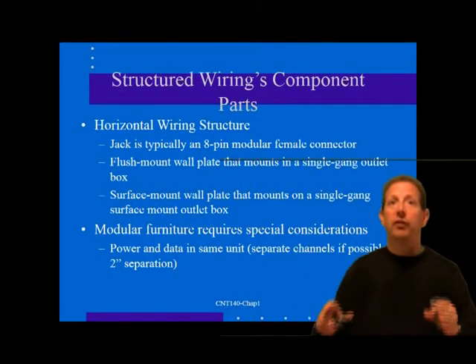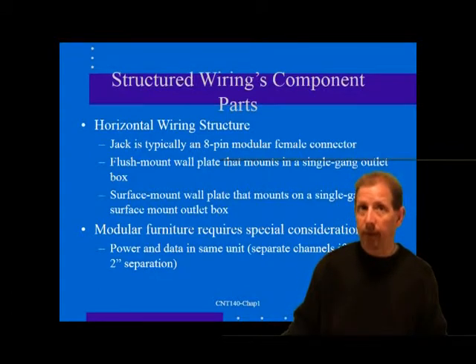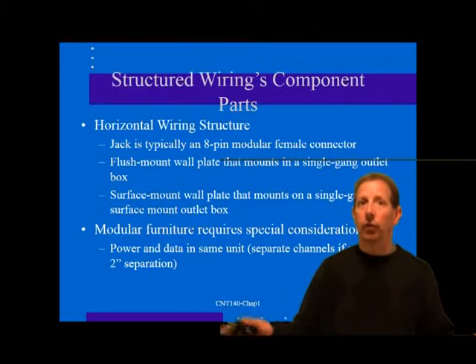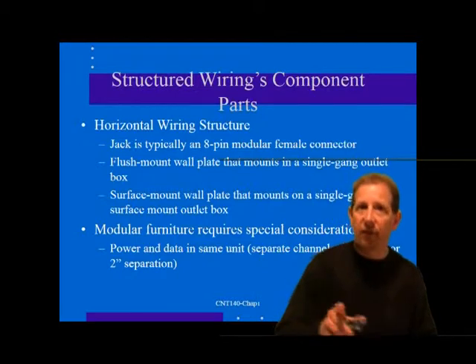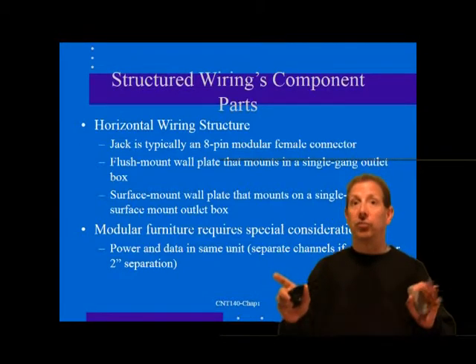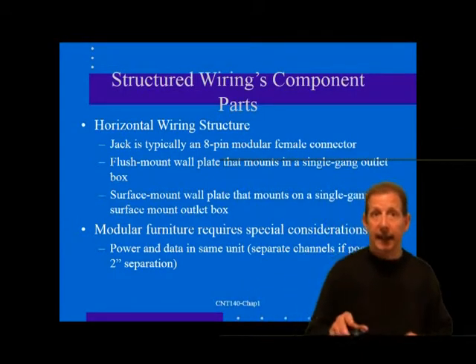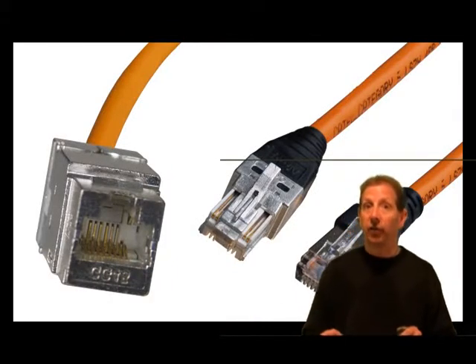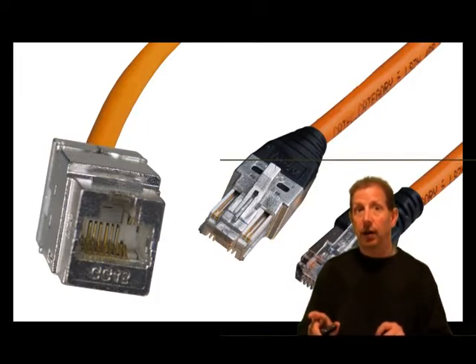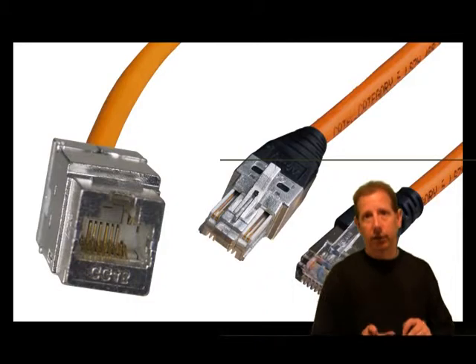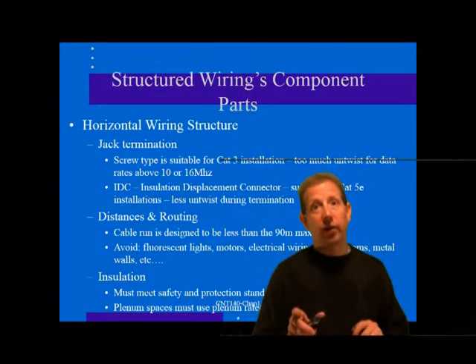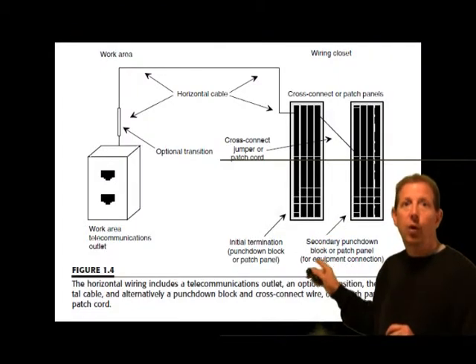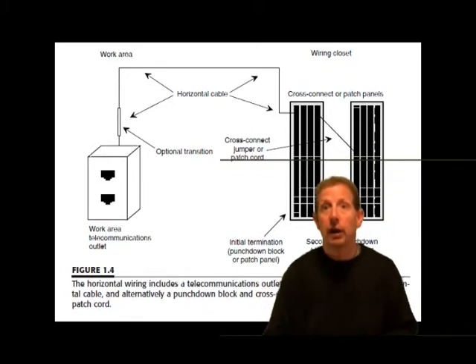Various wiring standards place special qualifications on horizontal wiring. You should make sure to use cable and components rated for the data rates you intend to use. If installing a Cat 5e facility, you must use Cat 5e rated jacks, cable, patches, and cords. If you use a cross-connect field between the station cables and a patch panel, the cross-connect wire must also be Cat 5e. The same is true for Cat 6 — all components including cables, connectors, and cords must be Cat 6 rated to achieve Cat 6 performance.